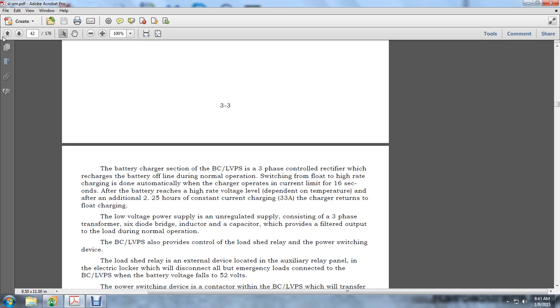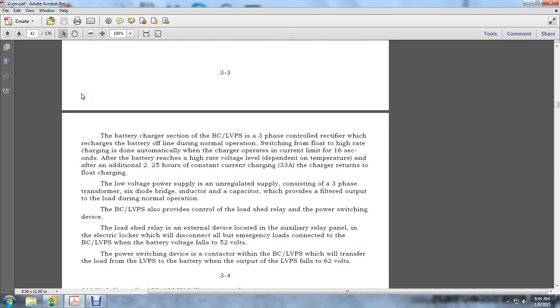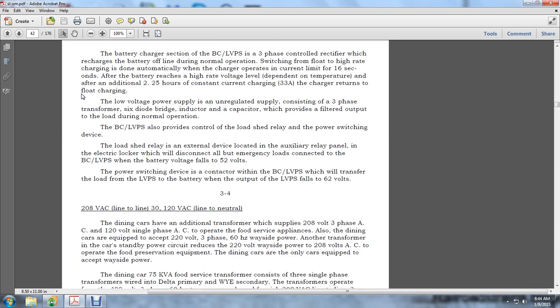The low voltage power supply's unregulated supply consists of three-phase transformers, 6 diode bridges, inductors, and capacitors provided in a filter output of the loading during normal operation. The BCL under the LVPS is provided to control the load shed relay and the power switching devices. The load shed relay is an external device located in the auxiliary relay panel in the electrical locker, which disconnects all but emergency loads connected to the BC LVPS when voltage falls to 52 volts. The power switch device connects the BC LVPS with the transfer load of the LVPC battery when output falls to 62 volts.